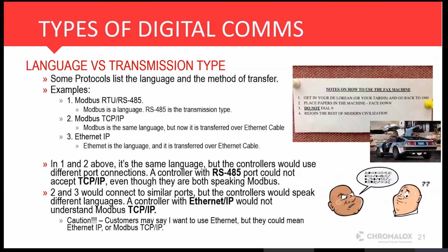Modbus TCP over IP is still Modbus. You're still talking the same language, but how the information is transferred back and forth is different. The TCP over IP is using Ethernet cable. So I have a nice little reference over there to the fax machine. If you can imagine picking up the phone and calling a fax machine, it's not going to go through, right? You get all those beeps and the fax machine doesn't know what you're trying to do. The two different devices just can't talk to each other. So that's kind of how it works with Modbus RS-485 versus the TCP over IP. Same language, different type of connection.